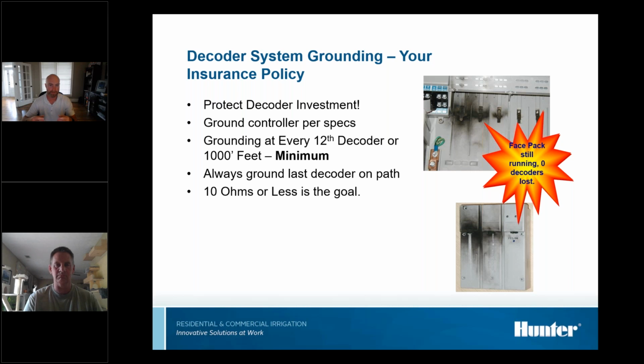We get thunderstorms pretty much every day in the summertime, so I would consider us a high lightning area. Florida is really high lightning because they get thunderstorms 9 months out of the year. So in those cases, or if you know the property that you're working on, for whatever reason, attracts lightning, maybe it's at the top of a hill, or it's been struck by lightning several times, you might want to ground a little bit more frequently than every 12 decoders or every 1,000 feet. You might want to go every 6 decoders, or every 500 feet.